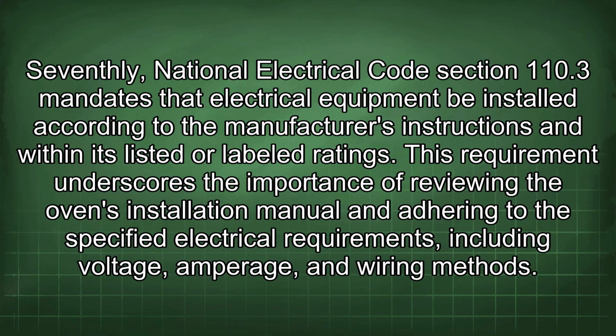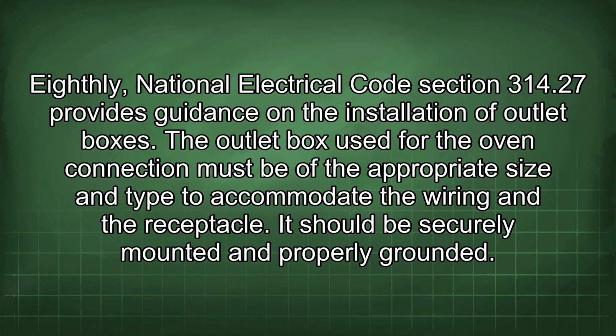Seventhly, National Electrical Code Section 110.3 mandates that electrical equipment be installed according to the manufacturer's instructions and within its listed or labeled ratings. This requirement underscores the importance of reviewing the oven's installation manual and adhering to the specified electrical requirements, including voltage, amperage, and wiring methods.